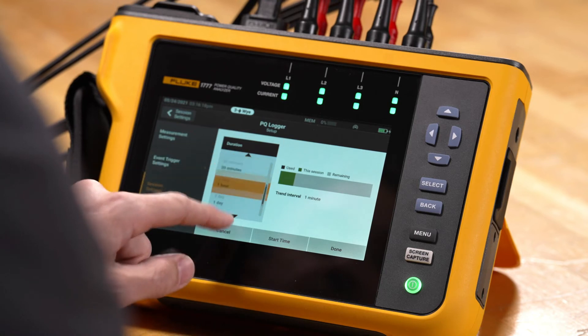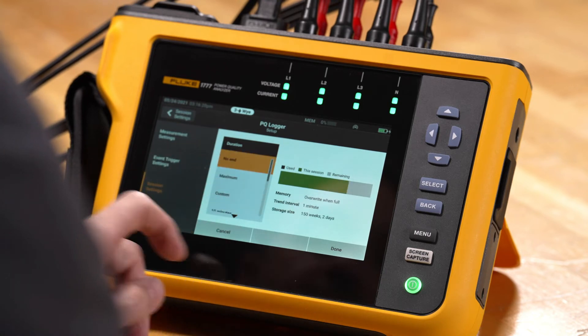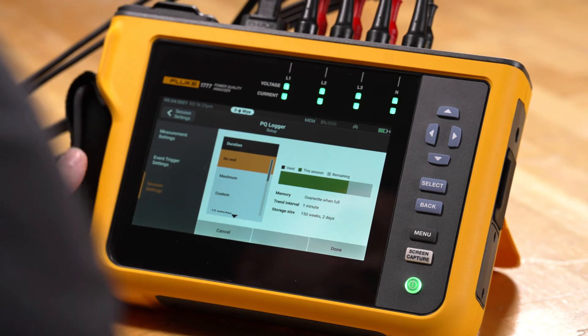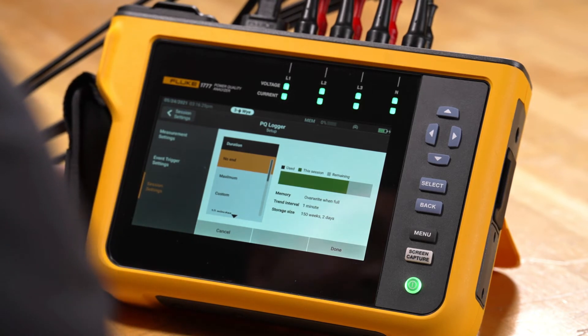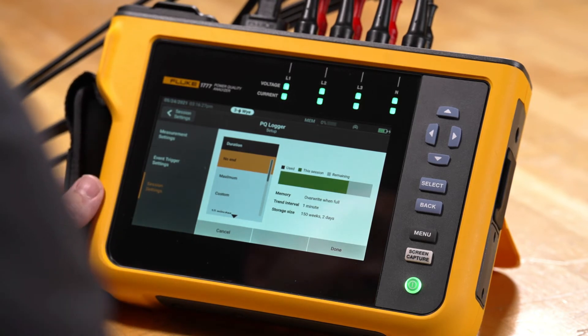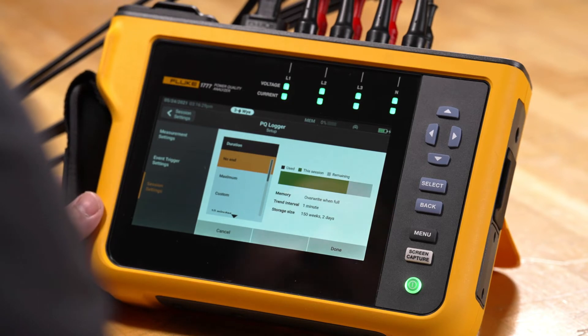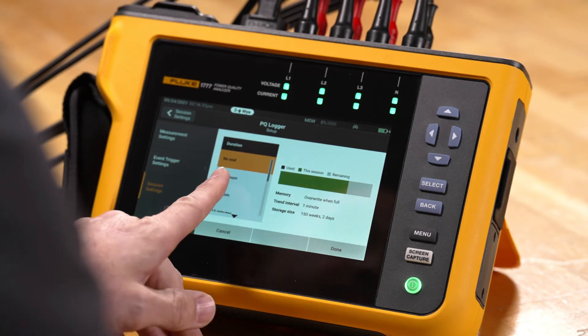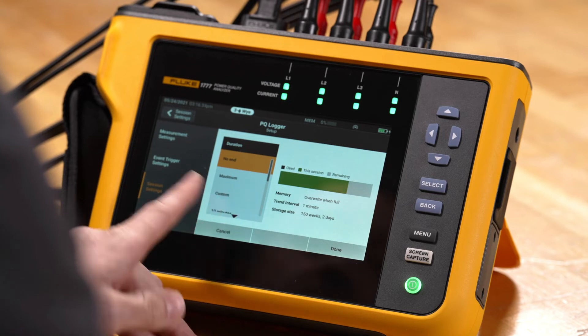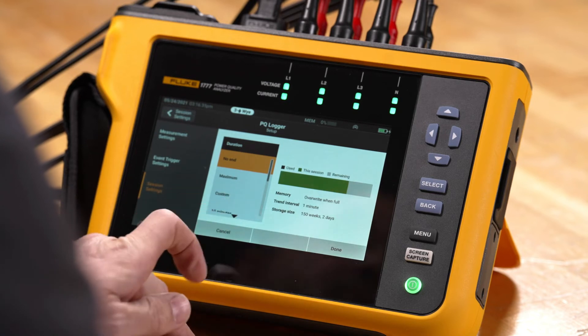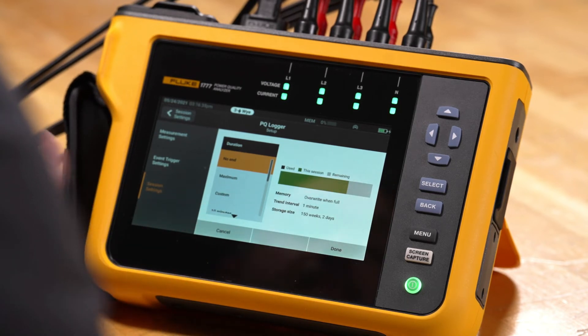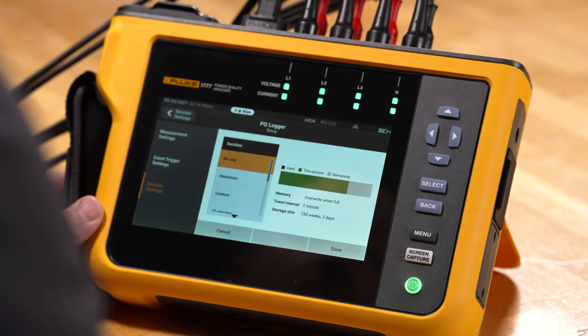In the duration settings we have the ability to set it to what we call No End. No End essentially allows us to record limitlessly until the memory fills up, and then it would just override itself. This way, if you need a semi-permanent or permanent recording installation, you could put it into a No End configuration and leave it there, coming back when you need data after an event has occurred.